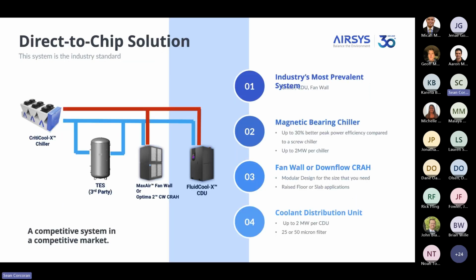So the first solution, as I say, is the CDUs, the chillers, and the fan wall. The magnetic bearing air-cooled chiller gives 30% better power efficiency compared to our competitors' screw chiller. And we have up to a 2 megawatt chiller. I'll show you the footprint on that because I think it's something that not a lot of our competitors have, but it's something that we are able to do in a smaller footprint. And our CRAH units come in downflow, upflow, front discharge, with left piping, right piping, top piping and bottom piping, whatever's available. We have our fan wall product, and of course our chiller.